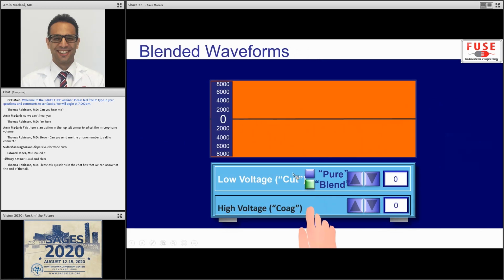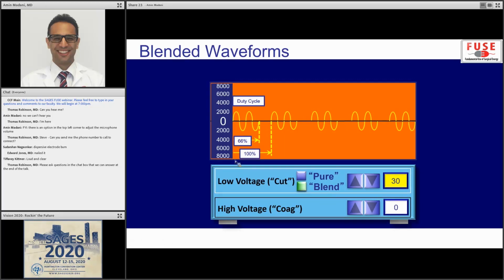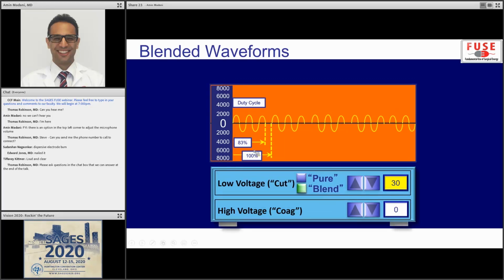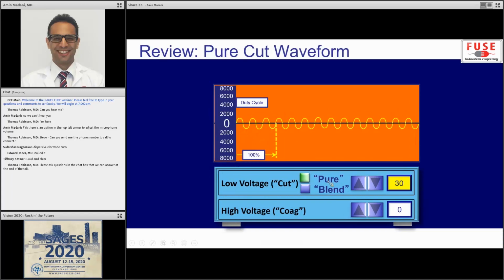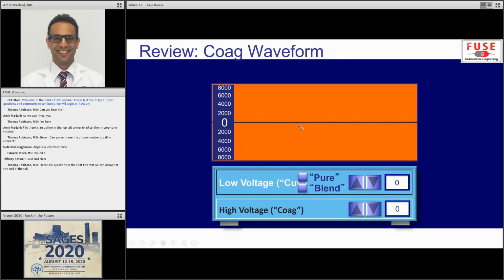What about blend? When you press the cut function, you can have it on pure or blend, which is basically a continuum. In cut, you had 100% duty cycle; in coag, you had 6%. Blend is somewhere in between — you can have 50%. Different proprietary devices have different functions, so you can have blend 1, blend 2, blend 3, varying the duty cycle. Again, pure cut is 100% duty cycle, low voltage.